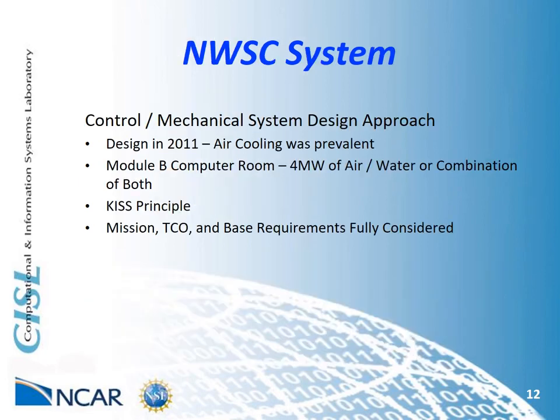The NWSC tried to balance all of these ideals as they approached the final design. As this step was winding down, air cooling was the more prevalent technology. So to be as versatile as possible, the NWSC Module B computer room was outfitted with the ability to cool 4 megawatts of load fully through air or through a mix of water and air cooling.